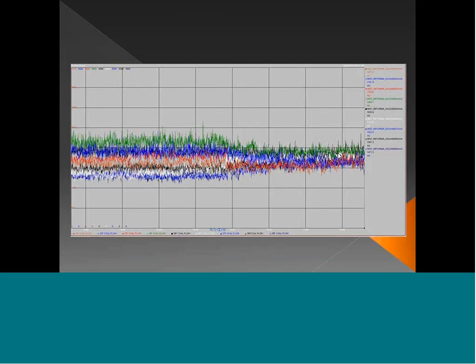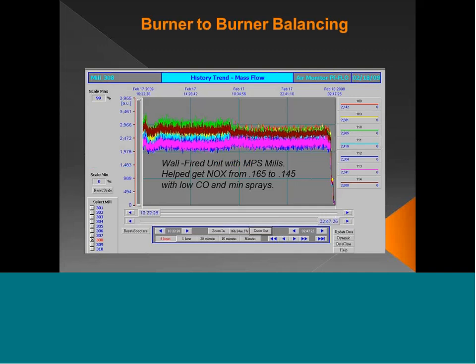the green pipe? Well, I'm sure the plant did try to get more coal off the green pipe, but by closing the valve too much, the velocity probably got too low, and they decided, well, this is more acceptable. This is where we will leave it. And so this was the distribution that they ended at. This is another case of a 7-pipe MPS pulverizer, where by balancing pipes on all the pulverizers, we were able to reduce NOx.